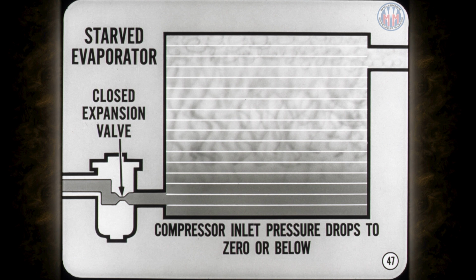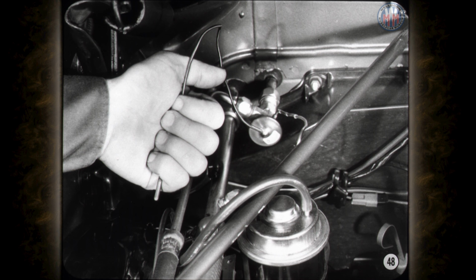Now, when a starved evaporator causes low discharge pressure, the evaporator's suction pressure will also be low. But here, unlike the low refrigerant condition, the compressor inlet pressure drops to zero or below. A starved evaporator is usually caused by a closed expansion valve. Check the expansion valve for opening by warming its thermal bulb in your hand. If the gauge pressure stayed down, the valve's not opening the way it should. All right, Fred, you've covered discharge pressure readings.